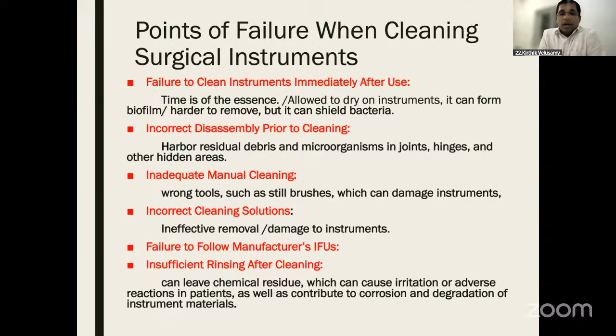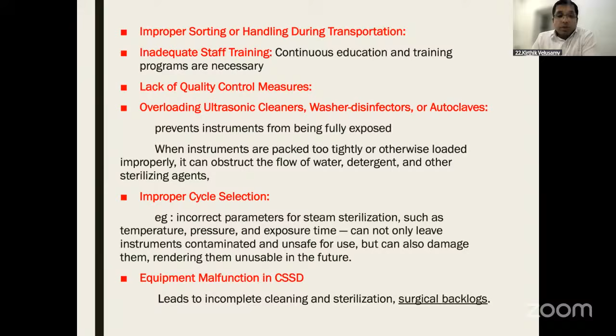The most important thing is adequate staff training. People keep coming, junior nurses and junior colleagues will be operating, and the nurse in charge is the one who needs to supervise initially before an individual takes charge of sterilization. Other factors for failure are overloading of ultrasonic cleaners and improper cycle selection. The last one is equipment malfunction. If you don't identify it at the correct point, it may lead to surgical backlogs. So we need to make sure everything goes well.